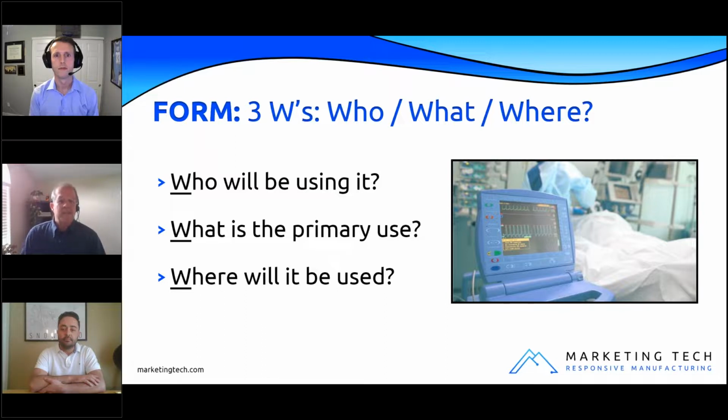Where will the equipment be in use? Ambulatory, in an OR, in a doctor's office? Constant environment or large variations? These questions point to materials, how parts are attached. Will shielding be required? And now a critical item in lab and med equipment, the appearance.